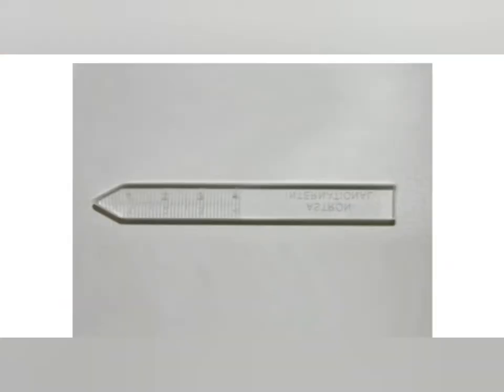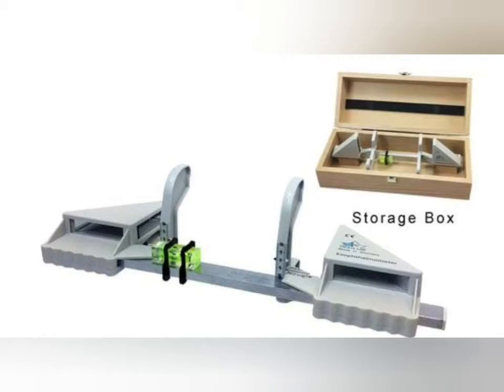This is Luedde's exophthalmometer. You can see this notch over here. You will place this notch on the lateral orbital margin and then measure the amount of proptosis. Another thing: suppose the person does not have the lateral orbital margin due to an injury. How will you measure? At that time you will use this Naugle exophthalmometer, which rests on the superior and inferior orbital margin, and then the procedure is the same as the Hertel exophthalmometer.